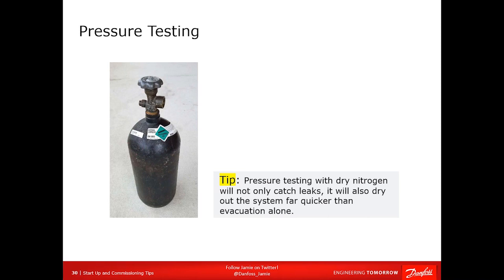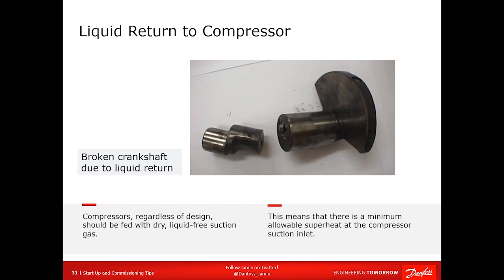However, you also have a tool in your arsenal, and that is dry nitrogen. Dry nitrogen is going to be your best friend. Not only does it get rid of copper oxide, it is also bone dry, all right, which means it has a very low vapor pressure. So as soon as you bleed it through the system and bleed it through the compressor, you will suck gobs of moisture, or whatever moisture happens to be in that oil, it will pull it out, all right? It is acting like a sponge. So do yourself a favor, always purge the system with dry nitrogen. You'll save yourself a ton of evacuation time if you need to dehydrate the system.